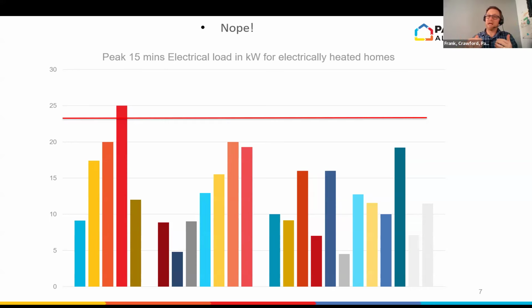And that is much less than the theoretical 24 kilowatts. Interestingly, there was a passive house that had one of the lowest peaks. It was 4.8 kilowatts. So it only took 4.8 kilowatts of electricity flowing to keep this all electric passive house warm on the coldest days of the year. So this is, again, preliminary data, but very encouraging that we probably don't need to upgrade above that 100 amp electrical service.